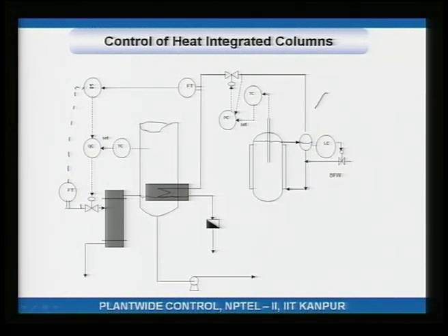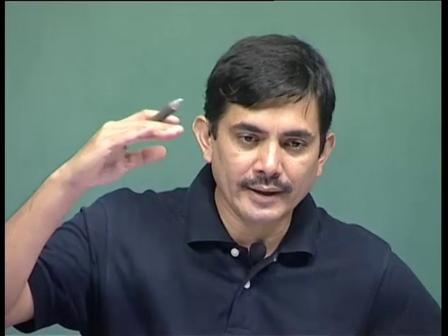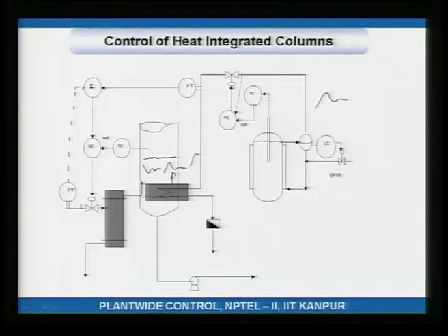And in this case, what happens is, if the boil up due to this fluctuates, then the total steam will fluctuate. Because the total steam is fluctuating, this QC, the total steam controller, will adjust this valve so that the total flow does not fluctuate. So there is fluctuation in the steam from the reaction section, and this is compensated for by opposite fluctuation in steam from the auxiliary reboiler, and when you sum it up, that would be relatively constant, and therefore as far as the tray is concerned, it doesn't see large fluctuations in the boil up, and the temperature remains relatively constant.